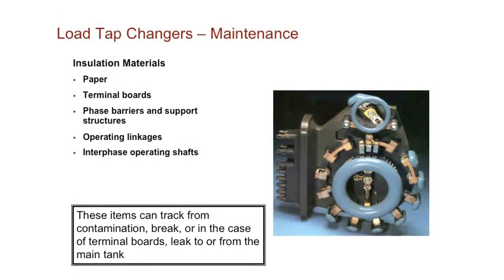Another component in there is insulation materials. You have paper, terminal boards, press board barriers. Linkages are made out of the insulation material as well. Basically, you're concerned with these breaking or cracking over time. Age has a lot to do with it. Previously, they used insulation boards. Today, they're using more epoxy or fiberglass type boards. So you have less breakage on them under vacuum. Most tap changers today will withstand full vacuum. A lot of your units 30, 40 years old will not withstand full vacuum. Some are partial vacuum, some are zero vacuum. It just depends on the type of tap changer that you have.